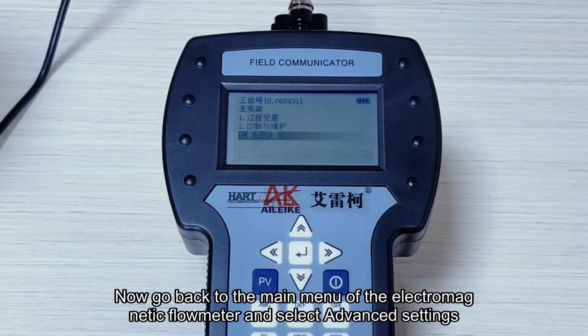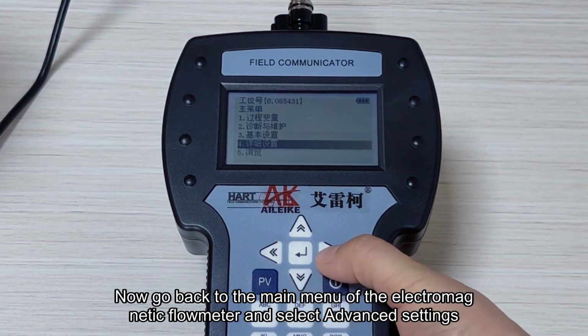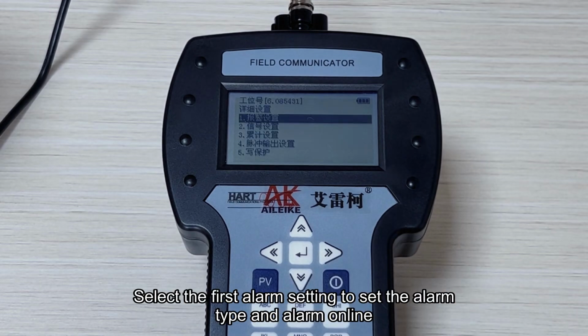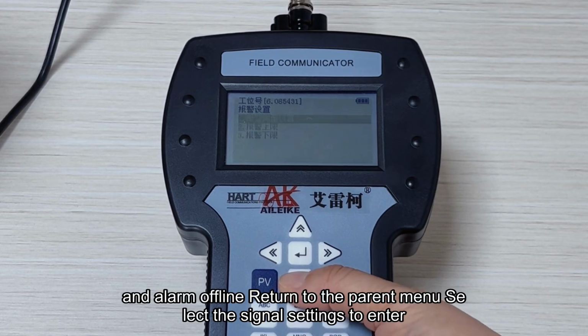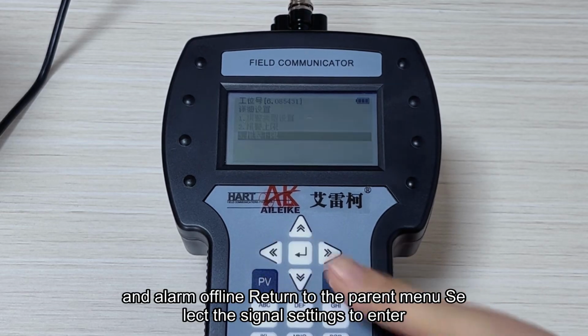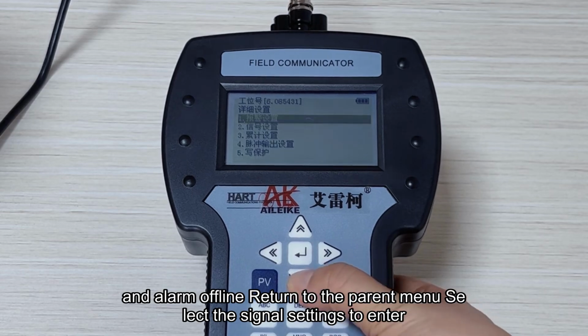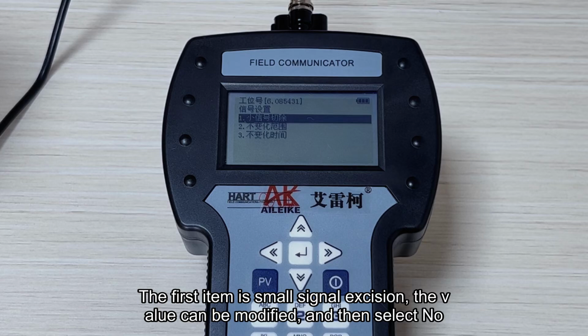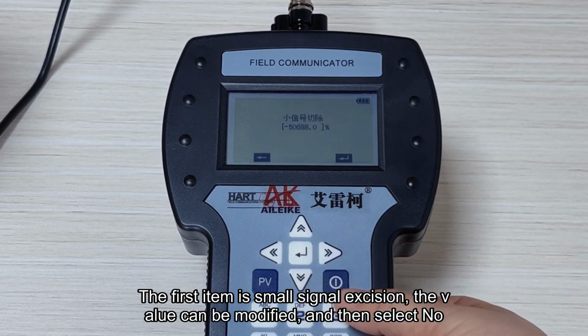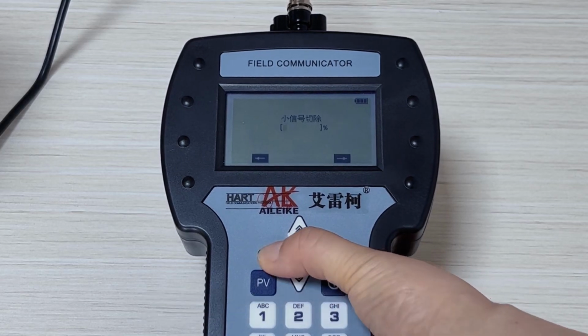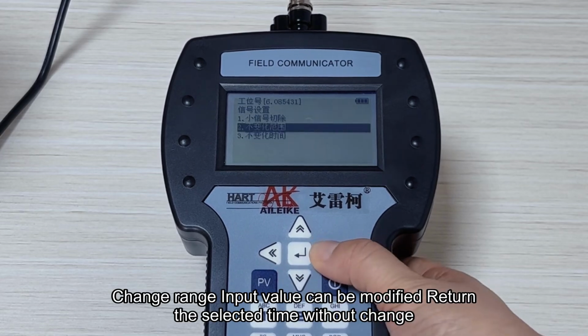Now go back to the main menu of the electromagnetic flow meter and select Advanced Settings. Select the first item, alarm setting, to set the alarm type, alarm online and alarm offline. Return to the parent menu. Select the signal settings to enter. The first item is small signal cutoff. The value can be modified, and then select the next item, change range. The input value can be modified.